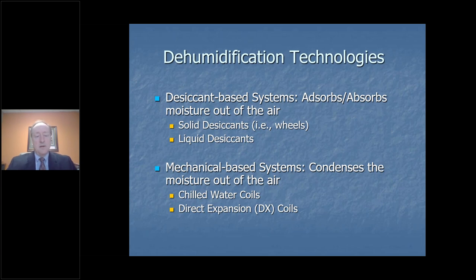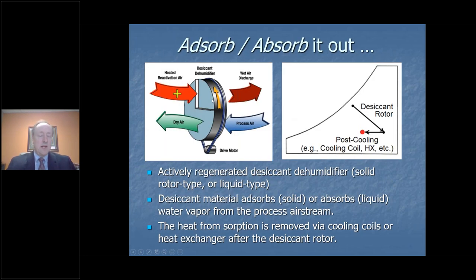But on the desiccant, it would be an air handler with a wheel in it, and this wheel moves very slowly. Oftentimes it's about 16 to 18 revolutions per hour. And what happens here, this is the air that we're trying to dry out. It could be outside air, it could be air from the space, or a combination of the two, but we call it process air. This is the air that's to dry out. It goes through this wheel that has been laden or impregnated with a desiccant product, oftentimes silica gel. And moisture is drawn off of this into the desiccant because the desiccant has a much lower vapor pressure. And then it comes out the other side a much drier air. It is warmer, but it's drier.